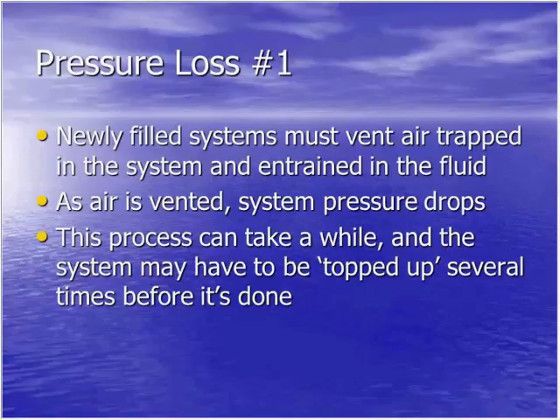That has to be vented out, or is usually vented out, with a properly placed air vent. And then pressure in the system will go down. As this air is vented, the pressure drops. And this process can take a while. It can take several days or a few weeks. And the pressure may have to be topped up several times before all the air is adequately vented out.